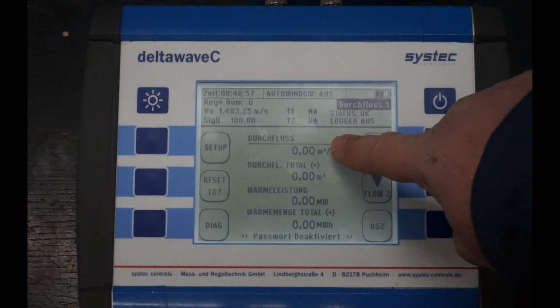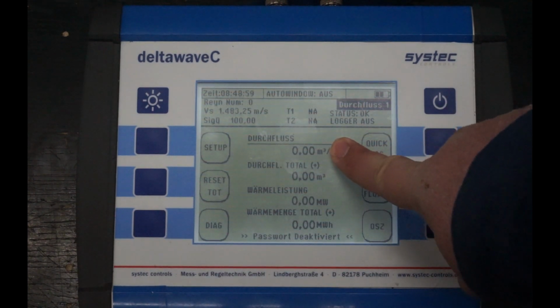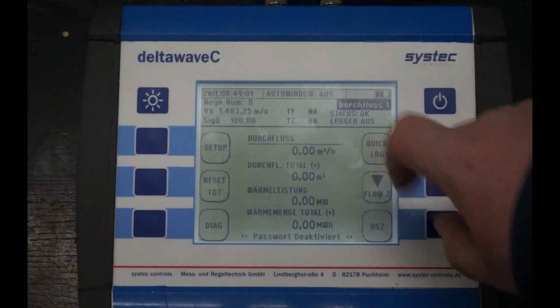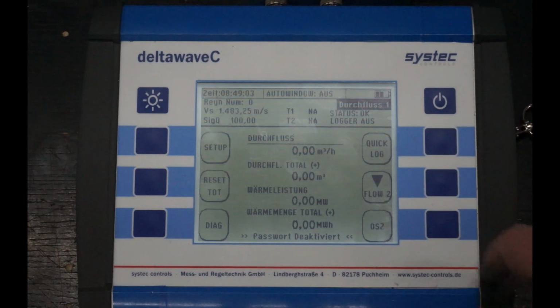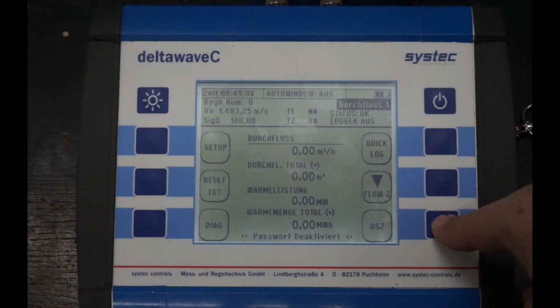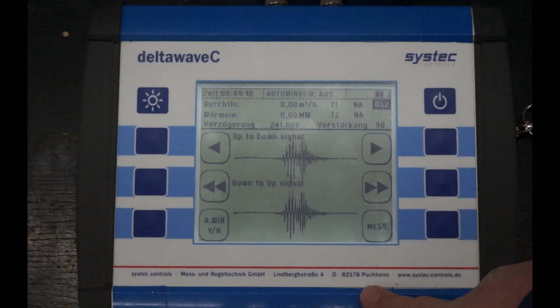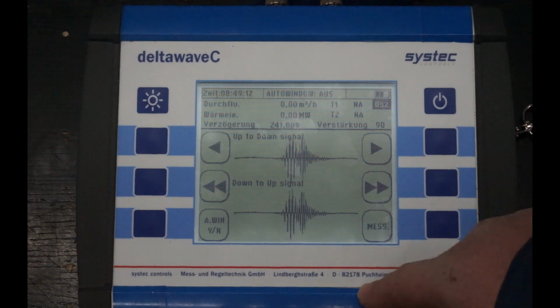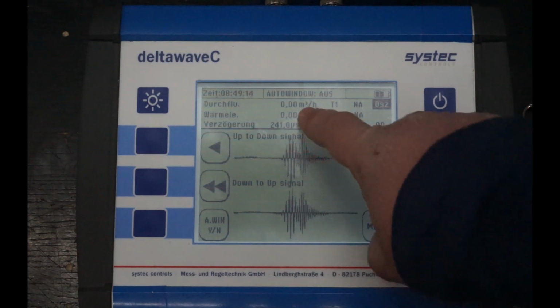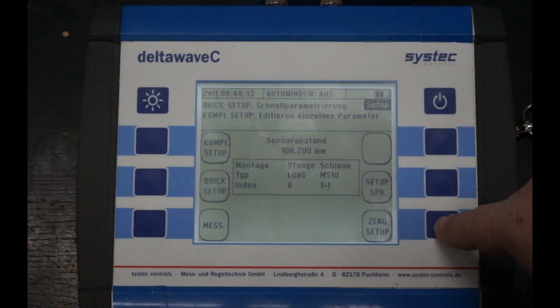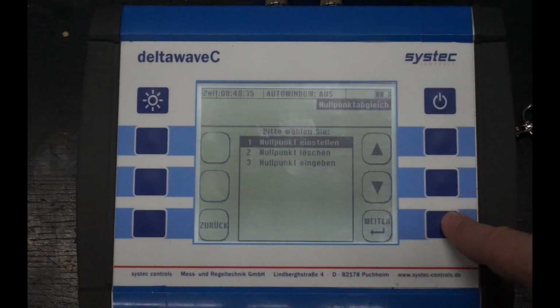Select the measuring menu on your deltawaveC. You should now see the actual flow on the display. By entering the oscilloscope menu, you may easily check if you have a good acoustic signal. Your signal should look similar to ours, with clear signal peaks and low noise in front of and after the signal. If possible, shut down flow in your pipe and perform a zero calibration.